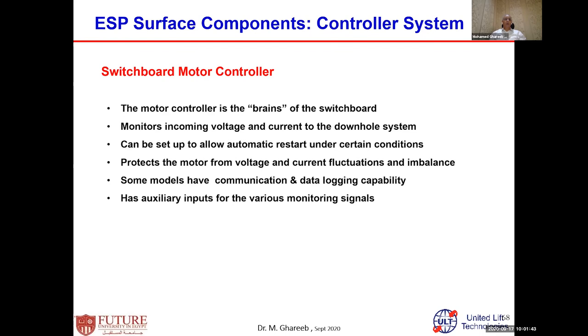The motor controller, as I said again and repeat, is the brain of the switchboard. The motor controller inside the switchboard monitors the voltage and current, and can help you set up automatic restart of the well. For example, if I have some downhole condition, such as a low flow rate, I need to put the well on a timer, so it automatically starts and stops. You can adjust based on time and a lot of other factors.